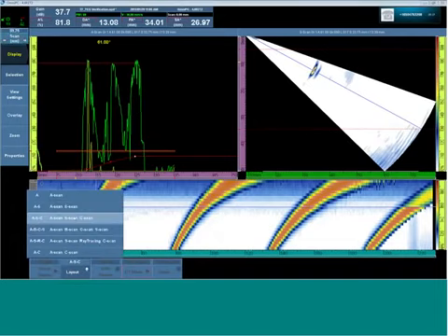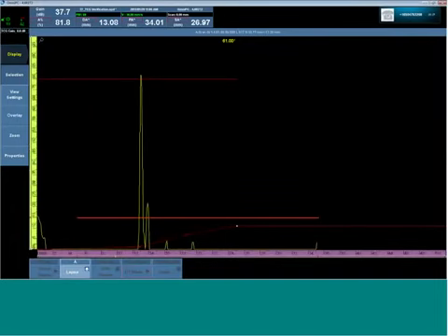But the point I'd like to emphasize is an A-scan is still an A-scan and can be calibrated in the exact same way. It's simply a matter of managing data and managing more of them and the tools we use to do that.